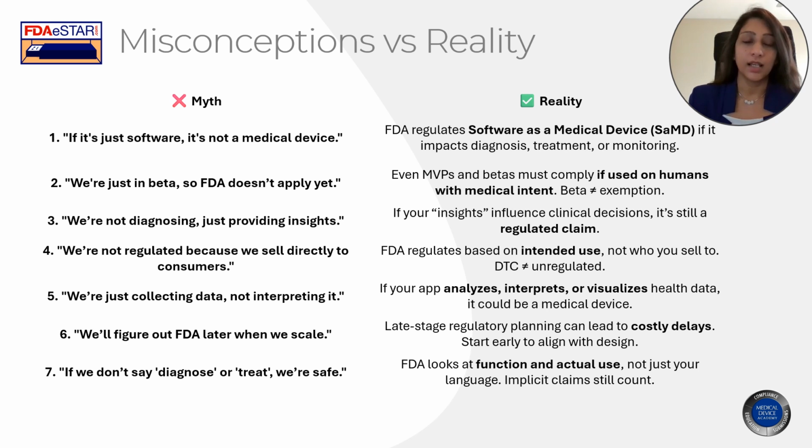We are not diagnosing, just providing insights. If your insights influence clinical decisions, it's still a regulated claim. We are not regulated because we sell directly to consumers. FDA regulates based on the intended use of the product and not whom you sell to. So even if you sell directly to the consumer, it might fall under a medical device. We are just collecting data, not interpreting it. If your app analyzes, interprets, or visualizes health data, it could be a medical device.